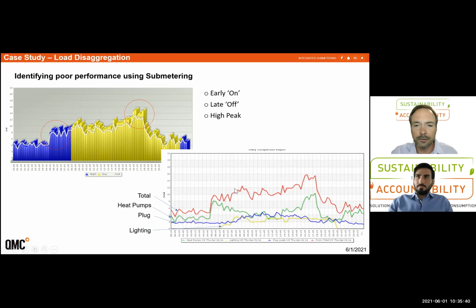You can see here in the red the total load. You can see that the plug load's pretty consistent throughout the day in blue. Lighting comes on during pretty much operating hours. That's great. And it was really the heat pumps that were set to turn on very early here, which they adjusted to a later setting as well. They were also turning on late in the day as people were leaving. So that was corrected, and you can see that it was really the culprit in the extra energy use within that floor.